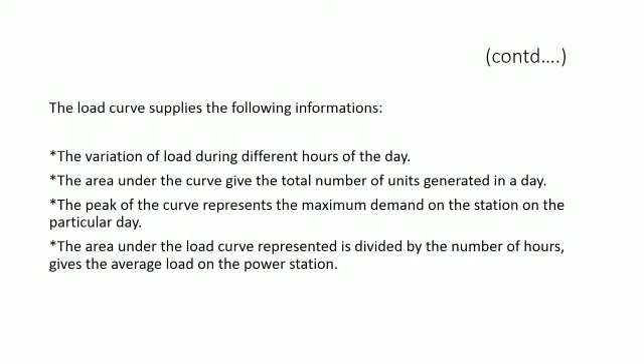Some of the information from the load curve: the variation of load during different hours of the day. The area under the curve gives the total number of units generated in a day. The peak of the curve represents the maximum demand on the station on the particular day. The area under the load curve divided by the number of hours gives the average load on the power station.